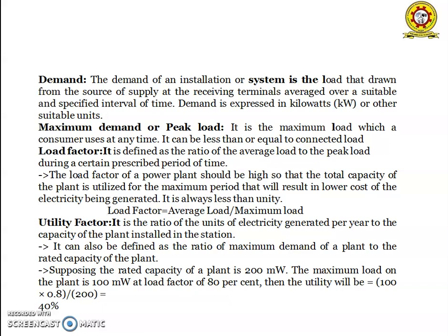A higher load factor means a greater average load, resulting in a greater number of power units generated for a given maximum demand. Thus, the fixed cost, which is proportional to the maximum demand, can be distributed over a greater number of units, that is, kilowatt hours supplied.